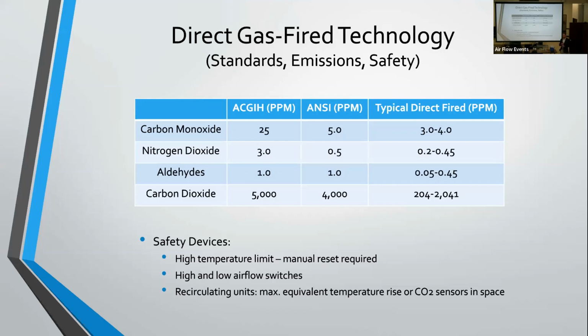So things like high temp limit switches that make sure you don't exceed your maximum 160 degree discharge temperature, and also make sure that you're not firing the burner at an unsafe firing rate. High and low airflow switches are another requirement. Your emission levels come down to how much air you're moving through that burner. That's the most important part of direct fire technology. So there are high and low airflow switches in the unit that make sure the proper amount of air is being moved across that burner at all times to achieve those low emissions.